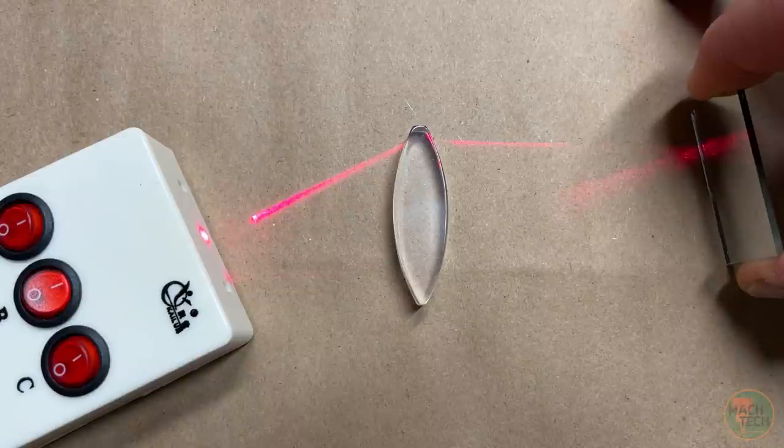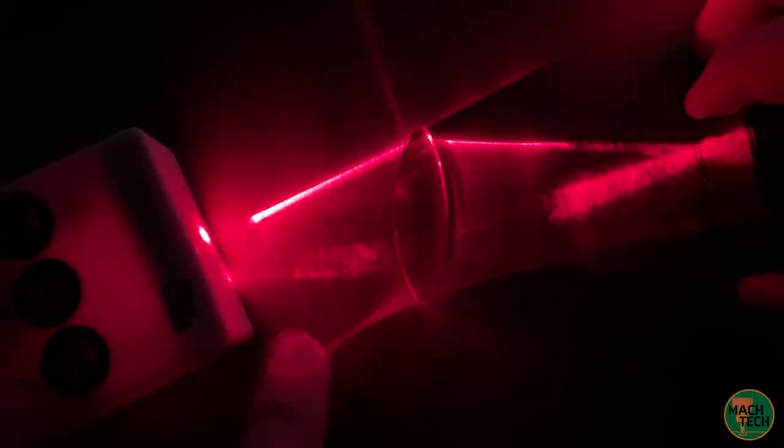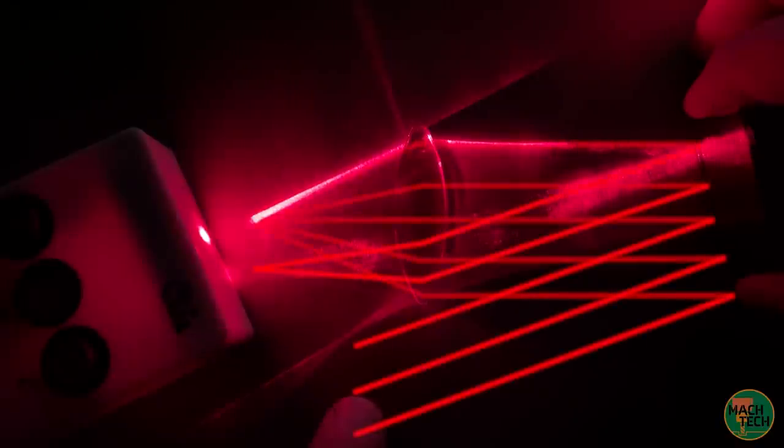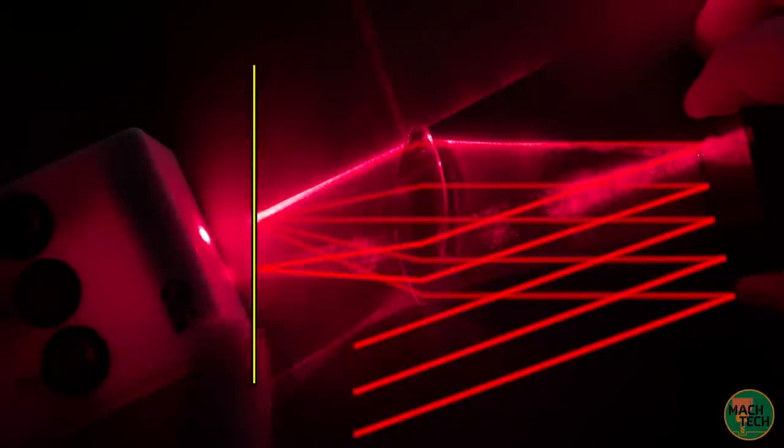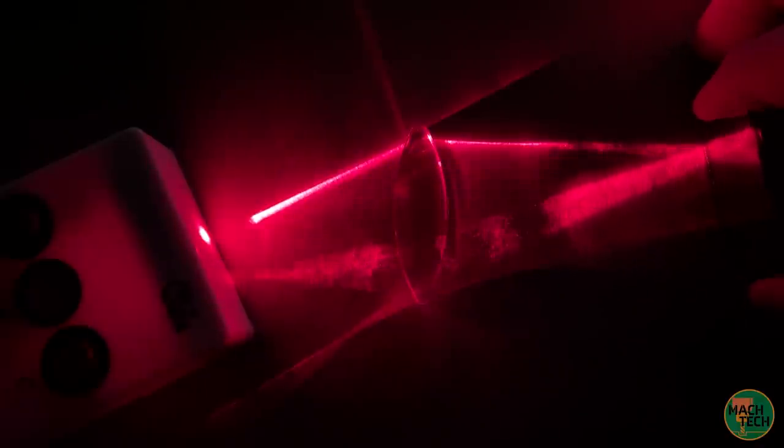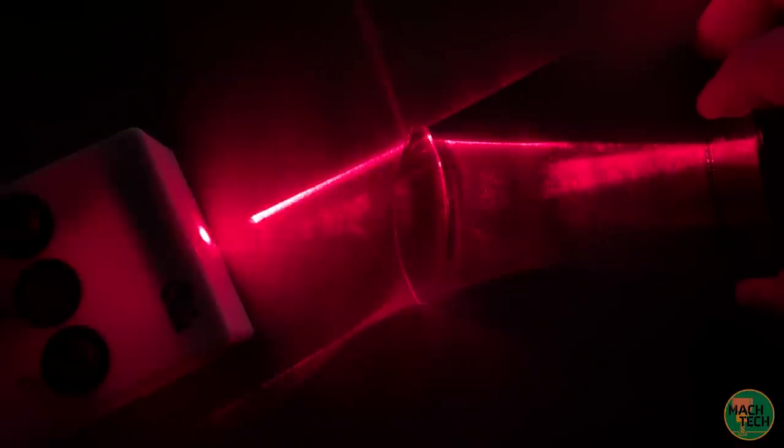Now I'm going to put the mirror back in there. And actually, you know, this is probably going to be kind of difficult to see, so let me turn off the lights and see if that helps. Okay, that's much better. Now, look at how the light ray reflects off of the mirror, re-enters the lens, and then gets refocused back over here on this side of the lens. Notice that it doesn't return exactly to the same point. Now, if we were tracing a bunch more light rays, you could see that the return light rays do focus back down onto the same plane. The same focal plane. But the focal point of the return light rays has shifted down a little. And if I rotate the mirror, you can see that the light hits a different part of the lens, and the return light ray focuses in a different spot over on the left. This is the same thing that's happening in an autocollimator. Now, imagine that the light source is the crosshair, and the point where the return light rays focus is the position of the crosshair image in the eyepiece.